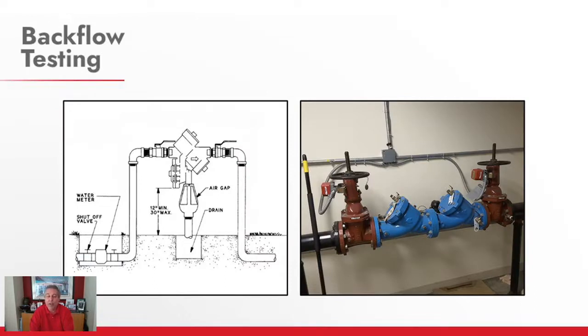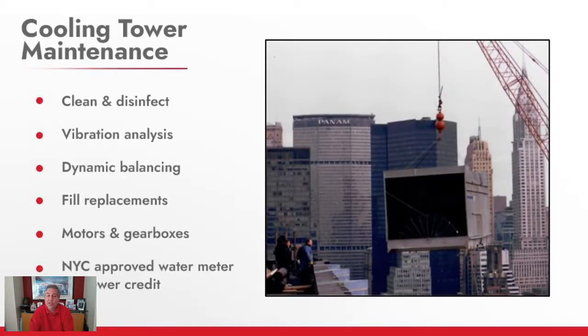As I mentioned earlier, especially with apartment buildings, with all of the increased sediment that's coming into the building these days, keep an eye on some pieces of equipment with all the moving parts, pumps, backflow preventers, anything with mechanical seals and O-rings. The wear and tear is also the second largest source of Legionnaires disease.